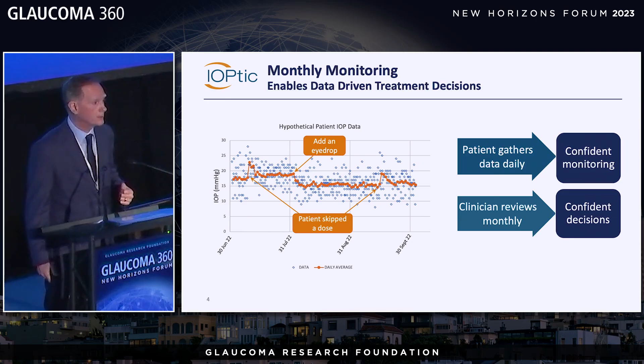And here's more of a deep dive on the sensor itself. On the left, the sensor diameter is 500 microns, and it's mounted on a clear PMMA housing that gets attached to the iris, and the largest dimension of the implant is less than 2 millimeters. These images illustrate how the interference pattern changes as the pressure changes. So we record images of the interference patterns, correlate those with the pressures, and that's our calibration curve.